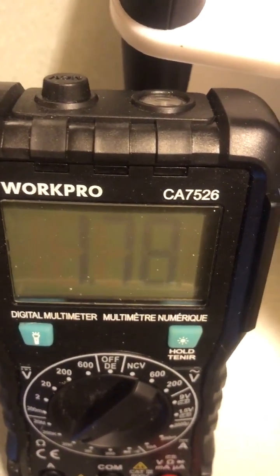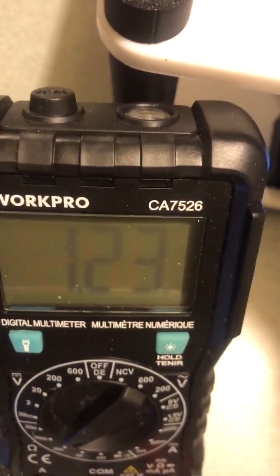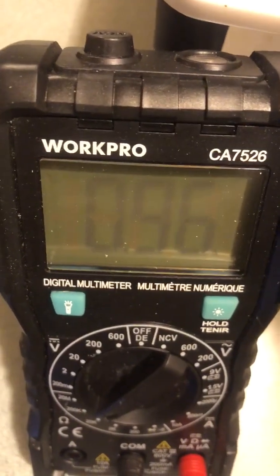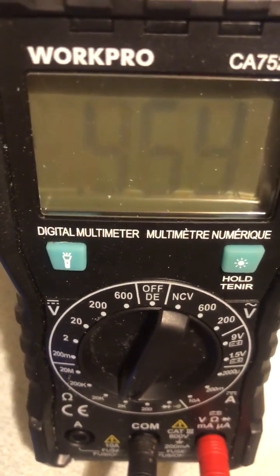There are all different settings. I think a standard is around 200 to 220 ohms, but it's an experimental thing. We want 400 ohms — we're at 700 now, so let's turn it down a little more. This is the first trimmer pot, so not far now.